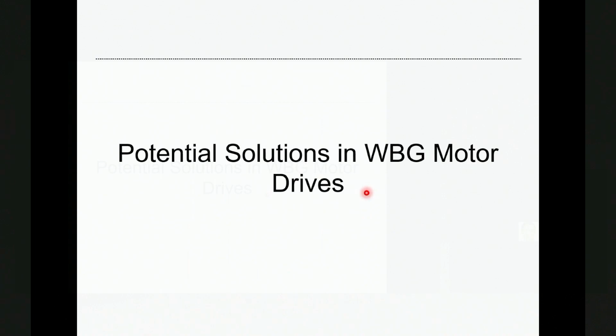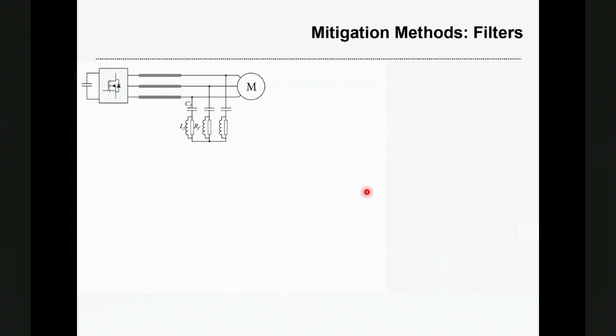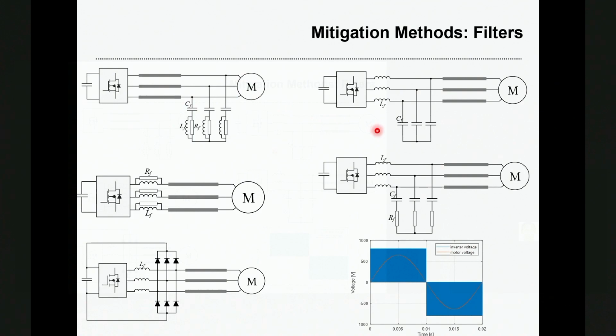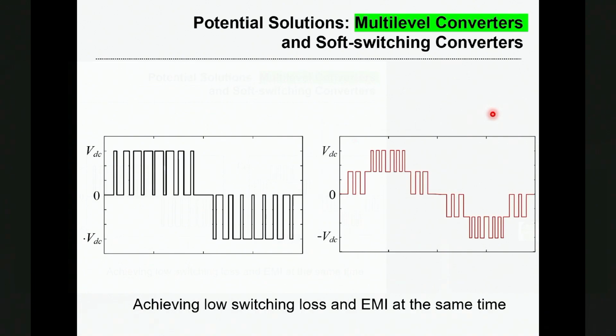Next, I will talk about some potential solutions in wide-bandgap motor drives to deal with the over voltages and other effects. The most used solutions are passive solutions where you use filters. For example, you can add filters at the motor terminal where you can match the impedance of the cable and the machine side. Then there will be less motor over voltage. You can also use various other types of filters, for example, the dV/dt filter and the sinusoidal filter, where you can remove all the harmonics and then reduce the voltage overshoot of the machine. However, under high current conditions, the passive filter can be very big, lossy, and also high cost in some applications.